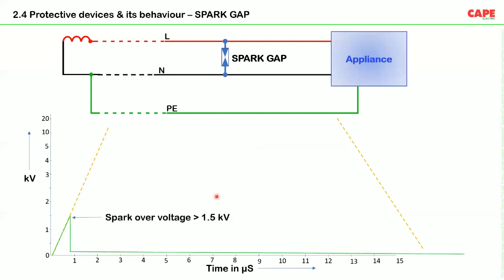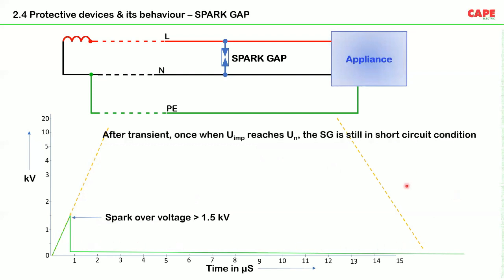The device is acting like a switch. That means once the sparkover voltage is reached, this device acts like a switch. Your line and neutral are connected. It is like a short circuit. After the transient is over, once the impulse voltage reaches the nominal voltage, the spark gap is still in short circuit condition, very dangerous. The spark gap will be in short circuit condition.